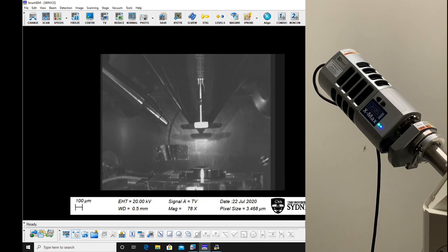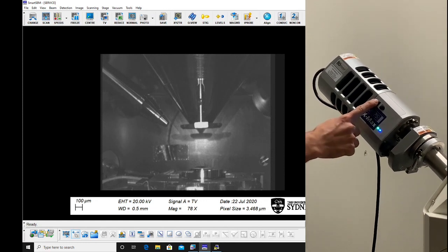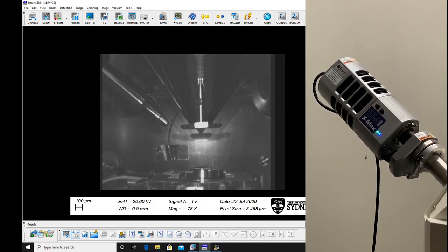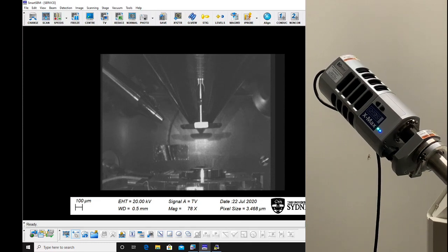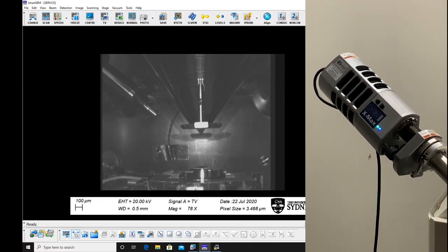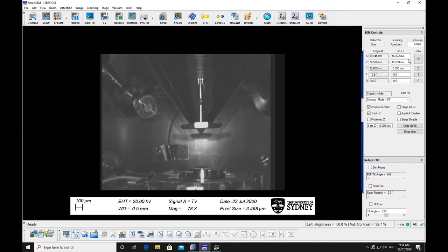Withdraw EDS detectors if need be by pressing the top button on the detector. Check that the specimen stage is not in a position to collide with anything on opening the chamber.